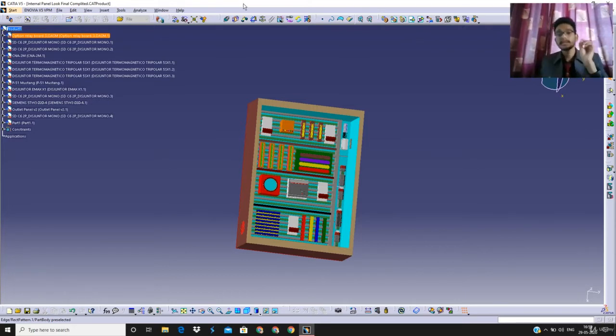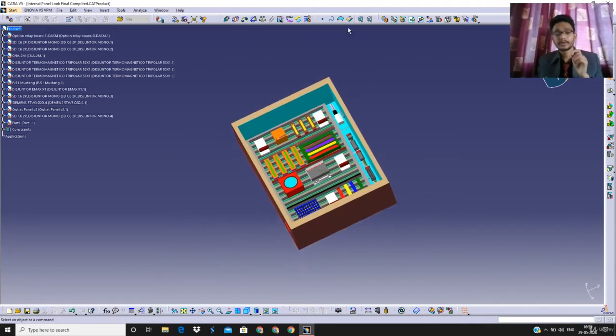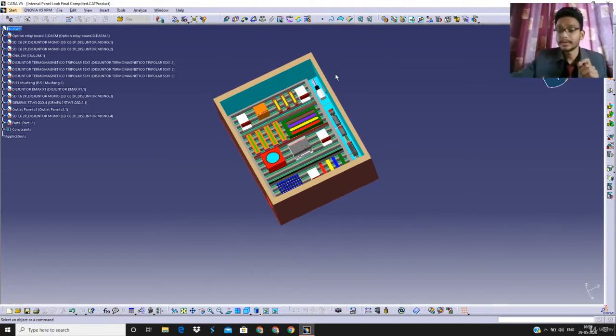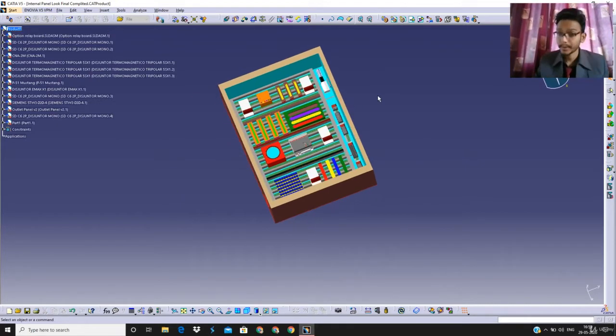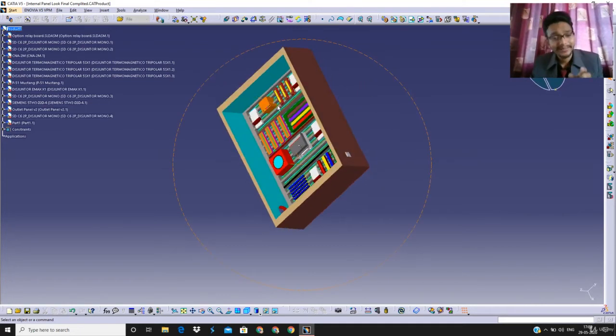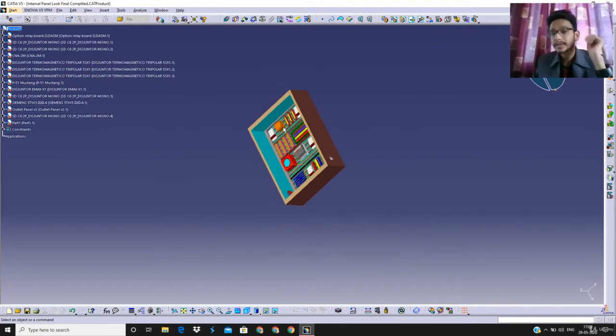The next thing is proper grounding buses. As we know, earthing is the most crucial part in any system, that is an electric system, to carry the leakage current directly in terms of protection. So all the cables, mostly the negative terminal cables in a DC system, should be grounded. All the devices with metal contactors must be grounded. All the panels with metal construction must be separately grounded to earth with a very low resistance path so that it can carry the leakage current and protect the person or operator working with it.